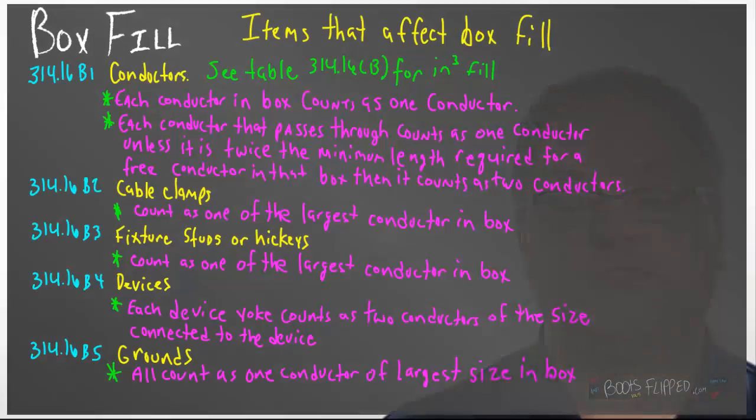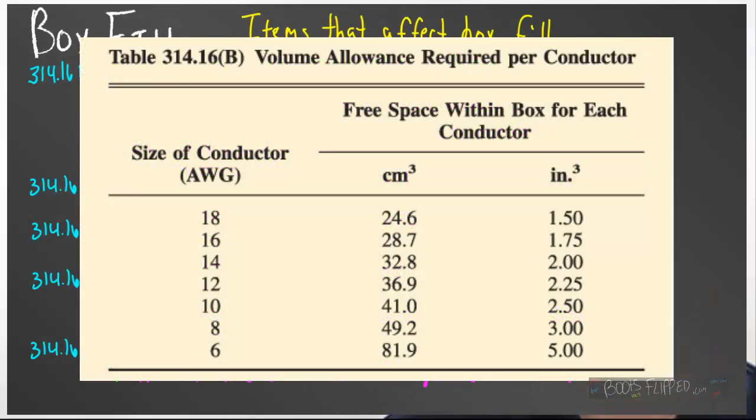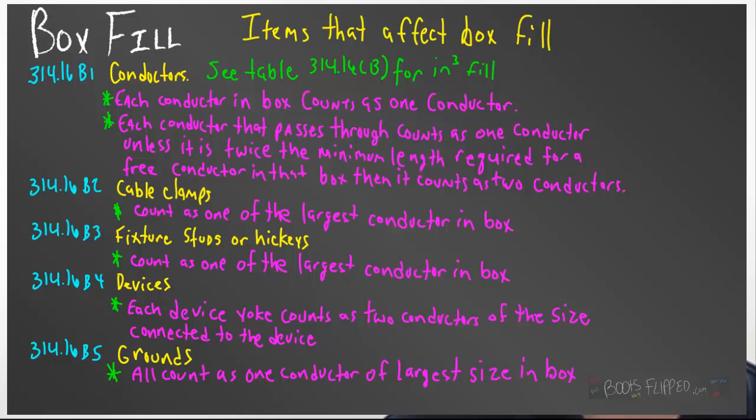There are items that affect your box fill, and they are these. First, your conductors. If we look at table 314.16b, it gives us standard size conductors and how many cubic inches they take up as far as room inside of a box. Take a look at that table.